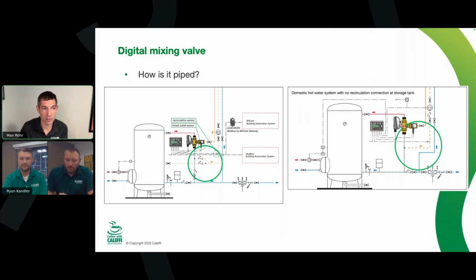So if this cold port is closed because the power was out for 24 hours and we're just getting the cold building up to temperature, this could be full hot. The digital mixing valve can do 100% hot or 100% cold. So we've got 100% hot going out to the building. This is fully closed. In that scenario, if you had a check valve right here, you wouldn't be able to get the water from the recirc line to go anywhere. It would be a deadhead situation. We want that to go back to the tank in that scenario. And if not, if the recirc is up to temperature, we'll just send that right back out here, and it can go up or down in that scenario. So that's a tricky one.